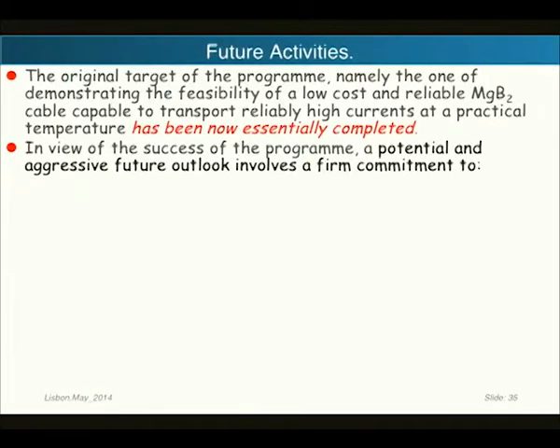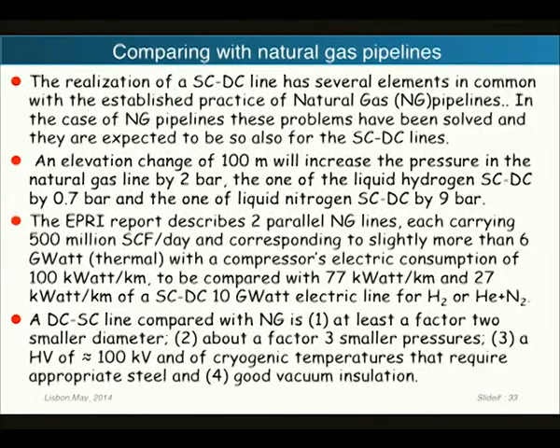You can see here the 100 kilowatts per kilometer of 6 gigawatt thermal, compared to 77 or 27 kilowatts per kilometer of electricity. Remember, there's a factor difference in electricity there. The DC line compared to natural gas is, of course, a factor 2 smaller in diameter, at least a factor 2 to 3. The typical diameter of the gas line here is 1 meter, and here we are talking about between 30 and 50 centimeters. The high voltage is of the order of 100 kilovolts, which is much lower than many of the demands of power lines, and which of course can be corrected. And the pressure is a small factor 3 lower: we are running at most between 20 and 30 atmospheres, while the pressure of the natural gas pipeline is 100 atmospheres.